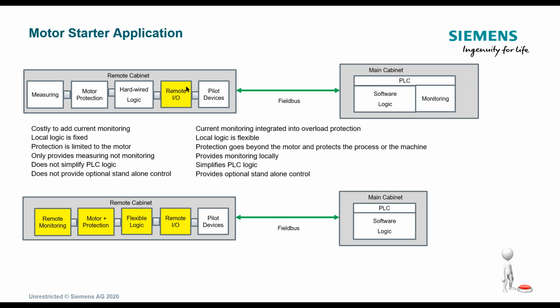But here with the remote cabinet, doing the remote I/O style, if you cut the field bus, of course, everything stops. Logic goes away because the logic's in the PLC, and all of the remote monitoring and everything stops because there's no communication back to the PLC to say, hey, what do I do if this happens? With the Simocode, I have the logic in it, and I'm able to evaluate it and keep moving with the set points that I have, or I can shut down, and it's all programmable.